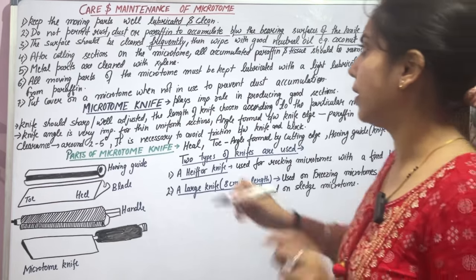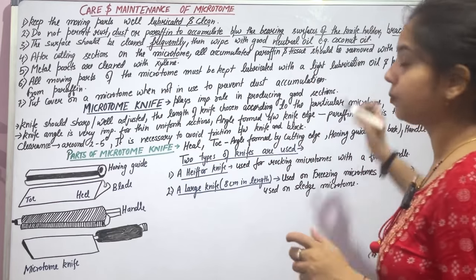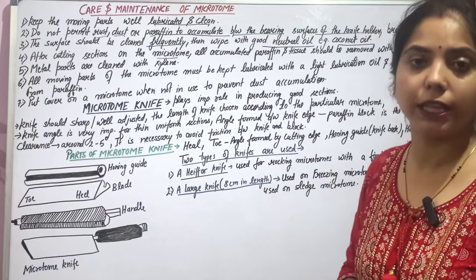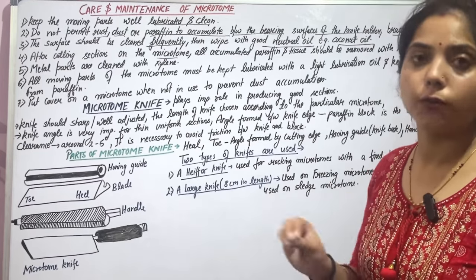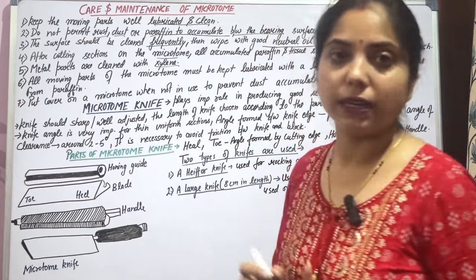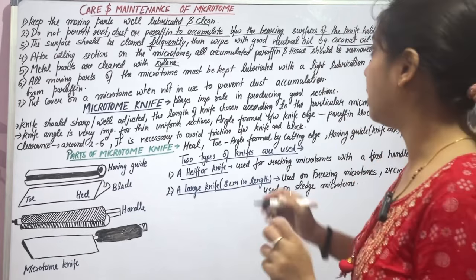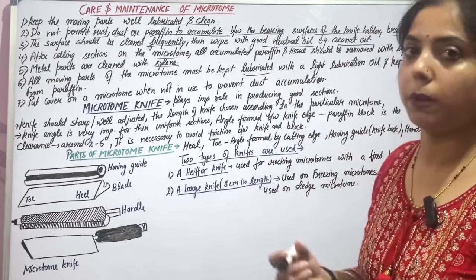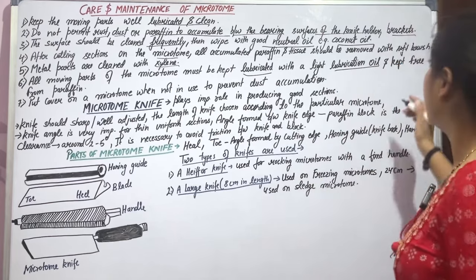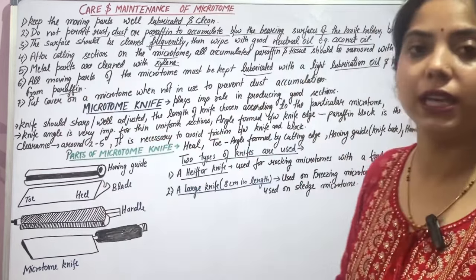After cutting sections on the microtome, all accumulated paraffin and tissue debris should be removed with a soft brush. Metal parts should be cleaned with xylene. All moving parts must be lubricated with a light lubricant oil and kept free from paraffin. Do not allow paraffin to build up on the microtome.